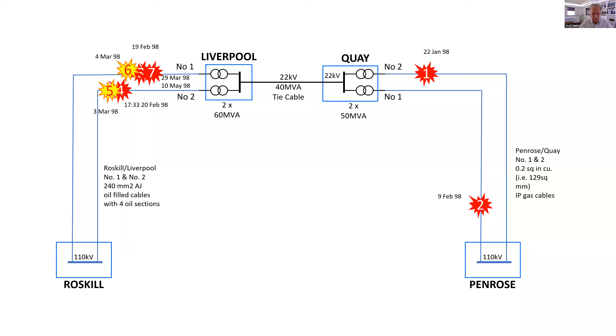Amongst other things, it found that some of the cables had not been properly installed originally, related to the thermal conductivity of the soil around them. There was a gas leak, I'm not sure if it was one or both of the cables, that had never been resolved. There was no asset management plan for the cables, maintenance requirements were poorly specified, and the risk of failure was not understood at any level in Mercury. It's possibly due to this last point that the planned cable tunnel from Penrose to the CBD had not made it to the Mercury board for approval. So this is really engineering failure at many levels.